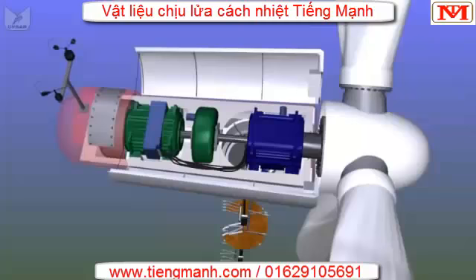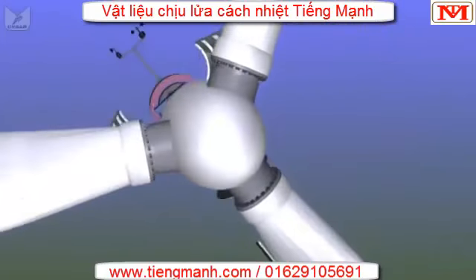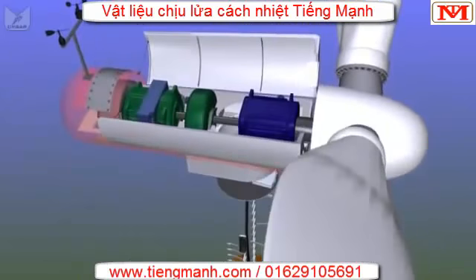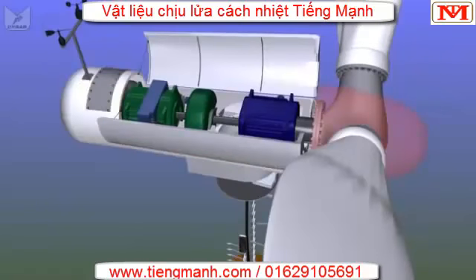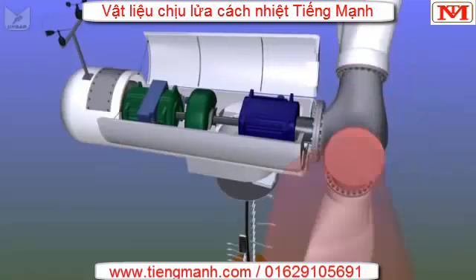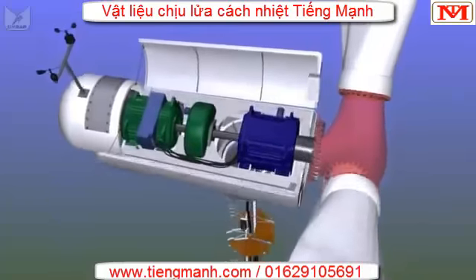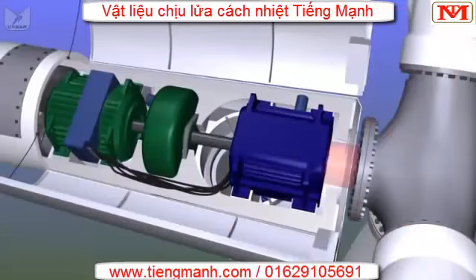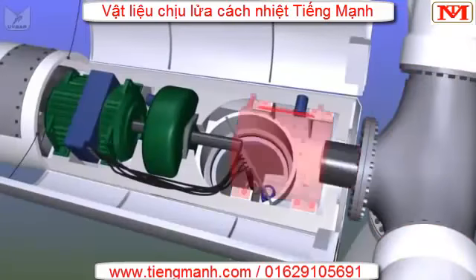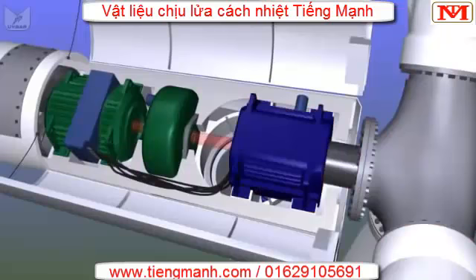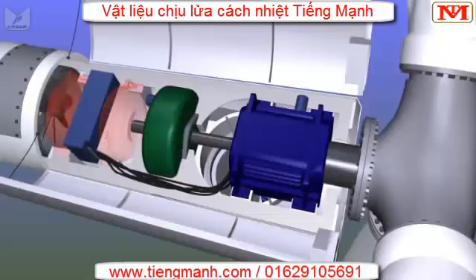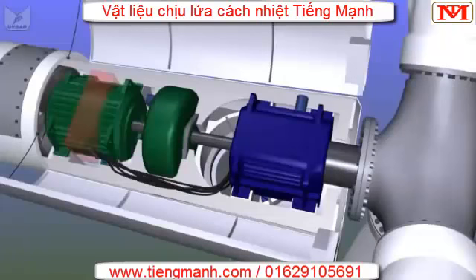The nacelle itself is just a fiberglass tube. At the front we have a similar fiberglass cowl protecting the hub, which is a steel casting on which we have bolted our three blades, and the blades can turn or pitch so that the angle they form with the wind can be varied. Out at the back of the hub we have a shaft which leads into the gearbox, then a high-speed shaft through a brake into a generator, and that generator then supplies the electrical power, as I say, at about 690 volts all the way back down the tower to the base.